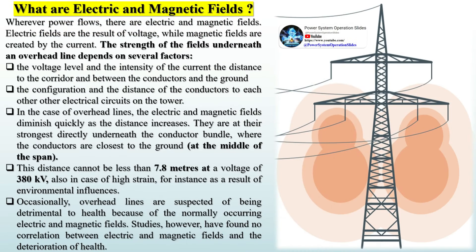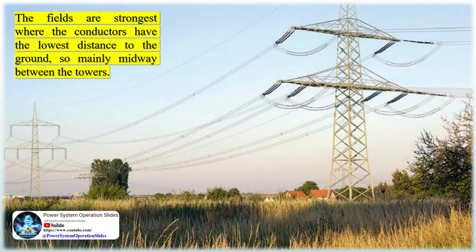What are electric and magnetic fields? Wherever power flows, there are electric and magnetic fields. Electric fields are the result of voltage, while magnetic fields are created by the current. The strength of the fields underneath an overhead line depends on several factors: the voltage level, the intensity of the current, the distance to the corridor between the conductors and the ground, the configuration and distance of the conductors to each other, and other electrical circuits on the tower. In the case of overhead lines, the electric and magnetic fields diminish quickly as distance increases. They are at their strongest directly underneath the conductor bundle, where the conductors are closest to the ground at the middle of the span. This distance cannot be less than 7.8 meters at a voltage of 380 kV. Studies have found no correlation between electric and magnetic fields and the deterioration of health.